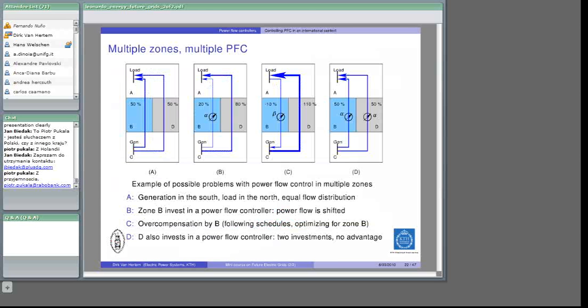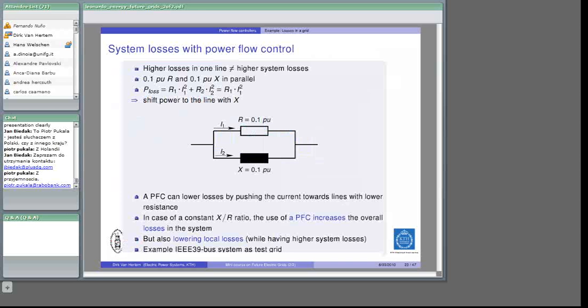As an example, I will mention the different losses in the system with different zones. First of all, higher losses in one line is not the same as higher system losses. As a very simple example, in the little scheme you see there, with 0.1 per unit resistance and 0.1 per unit inductance in parallel, the losses equation shows that it's only the current through the resistor that causes losses. So if you shift power to the line with the highest X, instead of the line with the high R, then you will have lower losses.